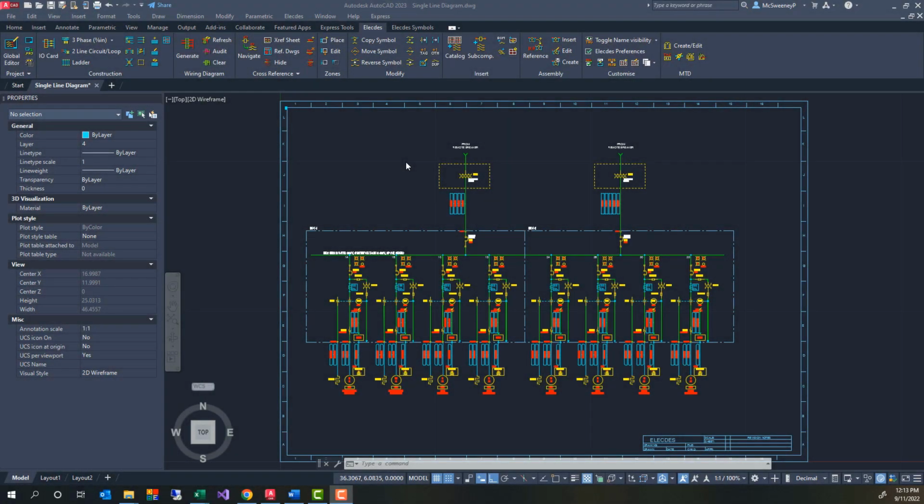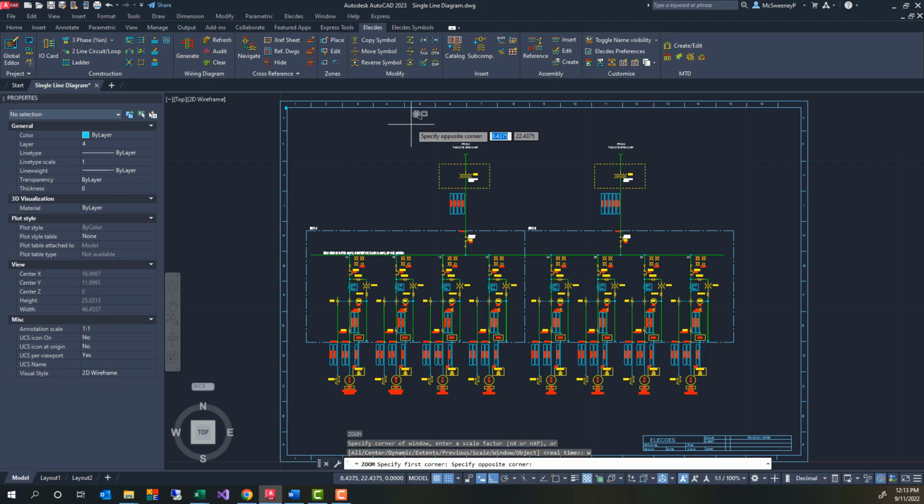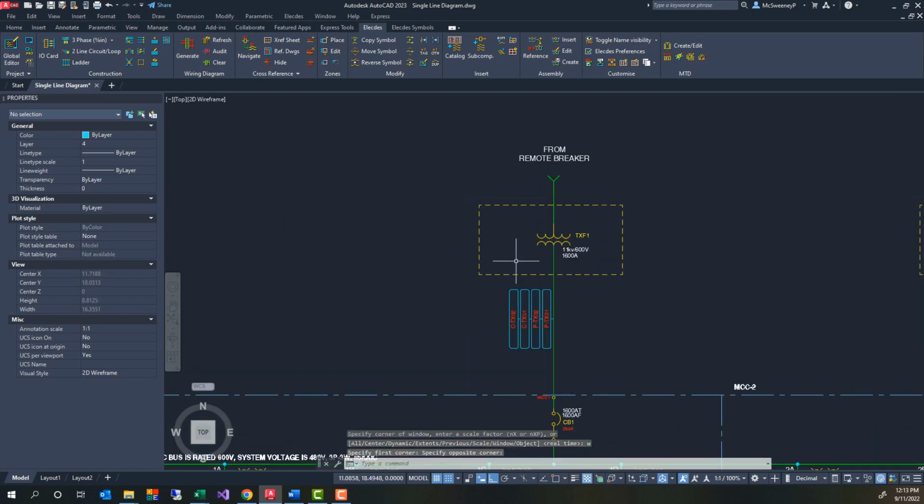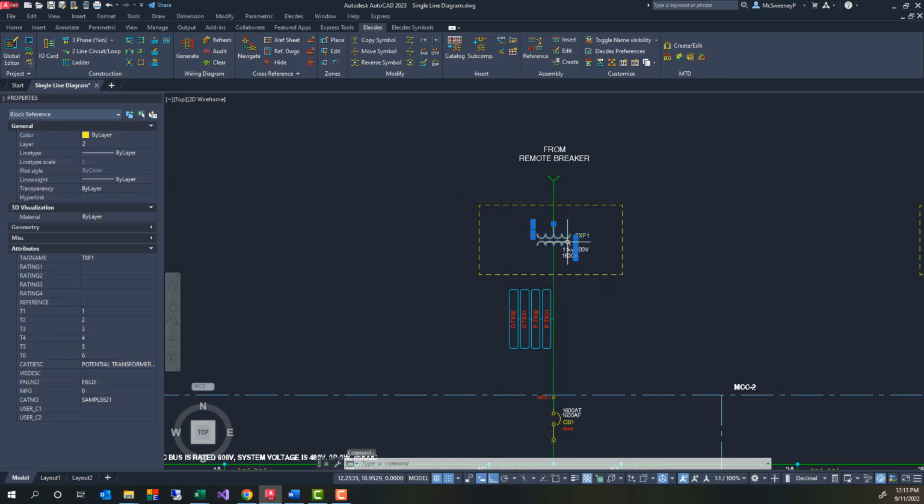Prior to doing cable routing, you will need upstream a cable list which contains cable specifications and termination data, i.e. where the cable goes from and to. Ideally, your project has electrical diagrams containing this information, such as this Paneldes single-line diagram. A Paneldes single-line diagram contains the terminating enclosures and devices, such as this transformer.